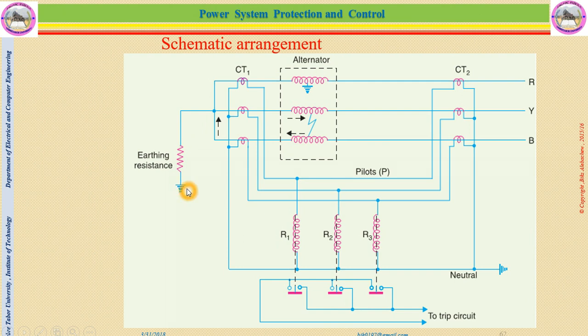Here is the ground, so this is the earthing resistance for that ground, and those three ground side terminals of the generator are connected to each other, and there are CTs. Let's call this group of CTs CT1. So CT1 is for the R, Y, B phases, and this is the alternator. Now those are the different types of faults; we'll return to the faults. And this is the other group, or the load side group of current transformers. We call it CT2.